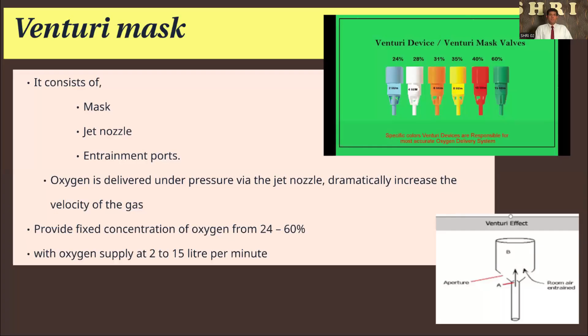So if you want to connect the patient to 28% FiO2, we can use the white color funnel here, and we have to give the specific flow rate. If you want to give 40% oxygen, connect the red color one, but we have to give 10 liters flow. If you are using the green color one, we have to use 15 liters, then it will give 60% FiO2. The patient is on 60% FiO2 with 15 liters with the green color Venturi funnel, but don't reduce to 10 liters and say now the patient is on 40%. No, in that case that's wrong, because everything depends on the physiology. So if you want to have the green one, 15 liters, that gives 60%. If you want to cut down, change the color and go for the specific amount.